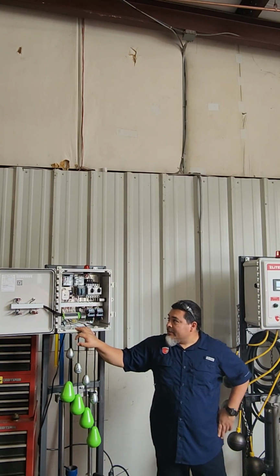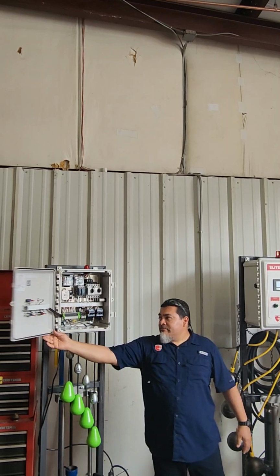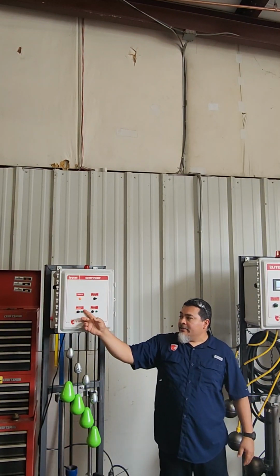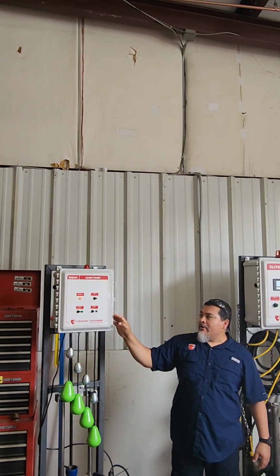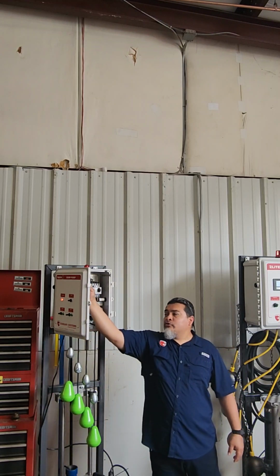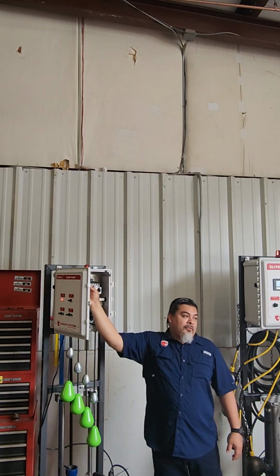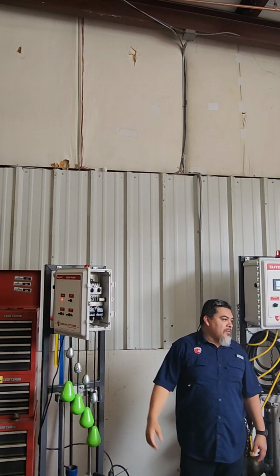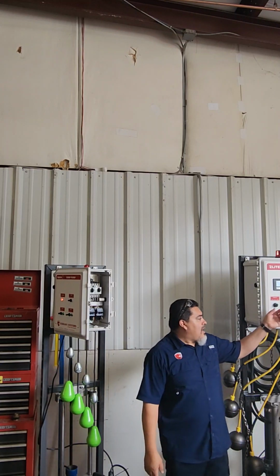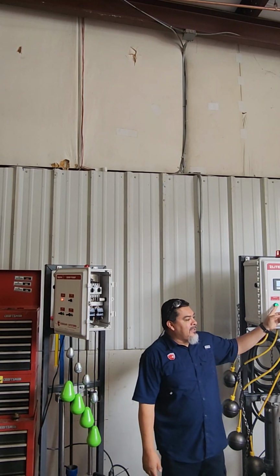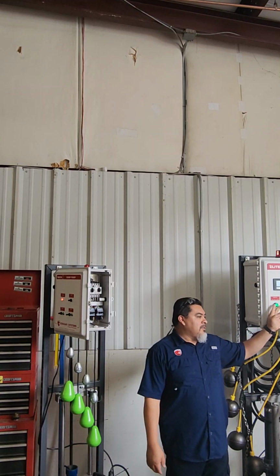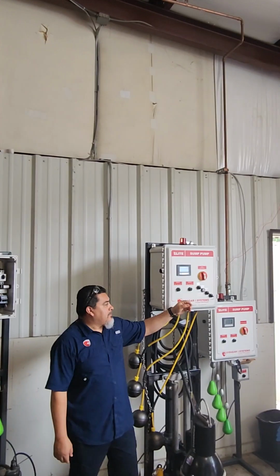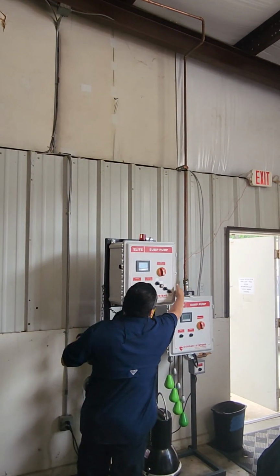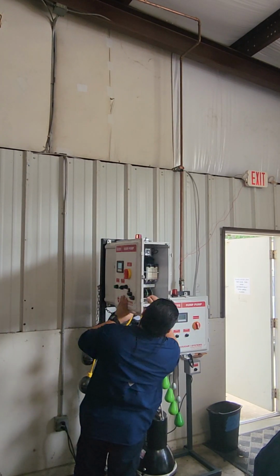And let me see, what else can I tell you? Of course, all of them have lights to indicate power, no power. If you don't see any power, more than likely your control fuse is blown or your high voltage control transformer or anything. For example, our green light indicates that the overload is good. If the overload is tripped, you hear the contactor still kick on, but the light won't activate.